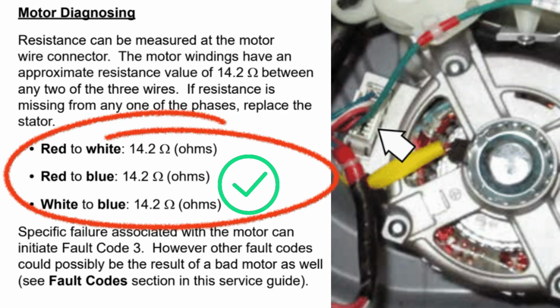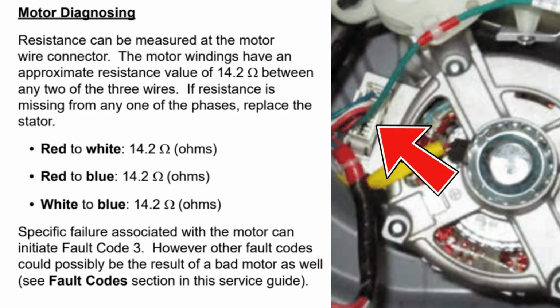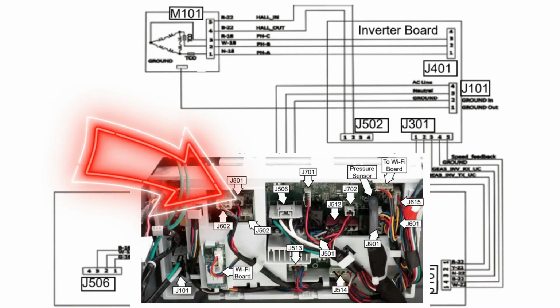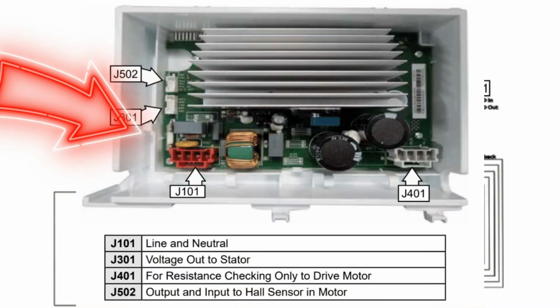You can test this at the harness connector. If you get unusual readings, disconnect the harness and test directly at the motor. If one winding reads drastically different from the others, that motor is defective. Once you verify voltage at the main board, check voltage at the inverter. You should also see 120 volts there.